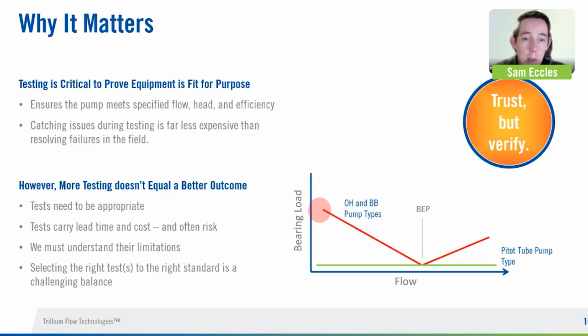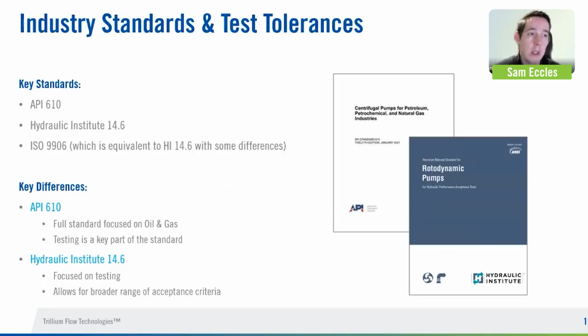We also need to understand the limitations. We need to understand what it's not going to tell us. So particularly for differences in fluid, as we're going to go into later, and making sure, as we talk about, there are a lot of conflicting standards. Picking the right one and selecting the right set of tolerances from that standard is not easy. And it's something that has to be done in collaboration with the pump OEM, really at the early stages of the project. So in terms of the key standards we'll talk to today, we're really going to talk to two. So we're really going to talk to API 610 and Hydraulic Institute 14.6.